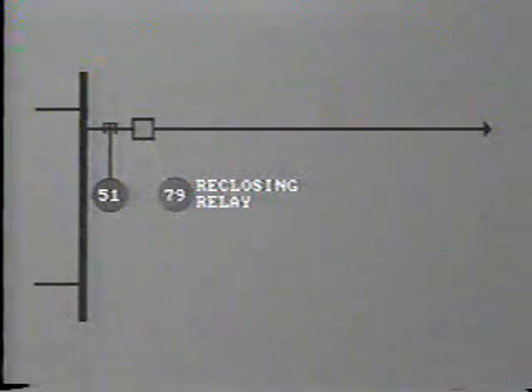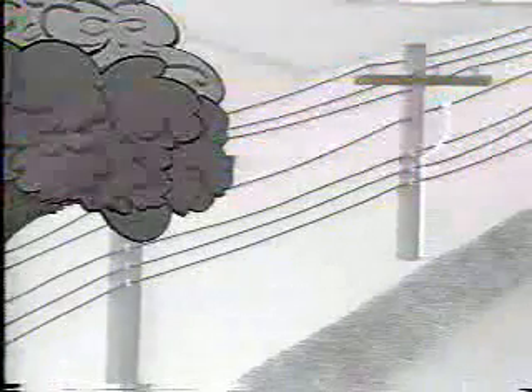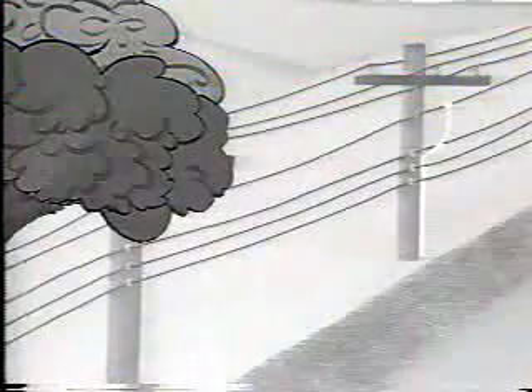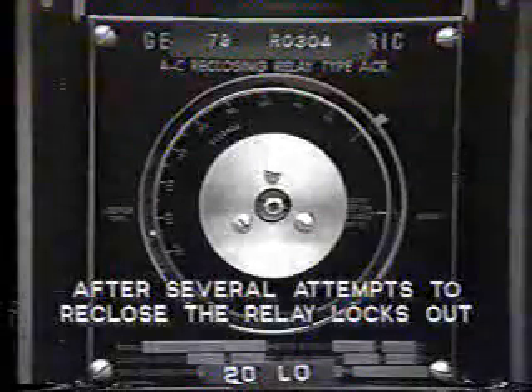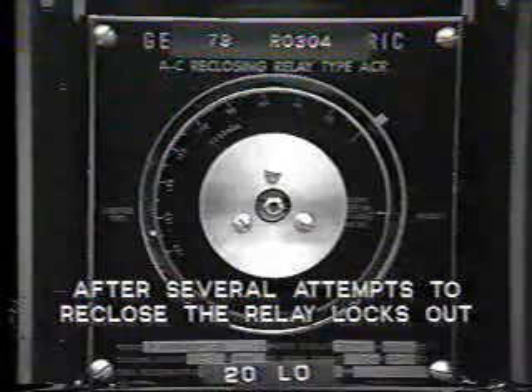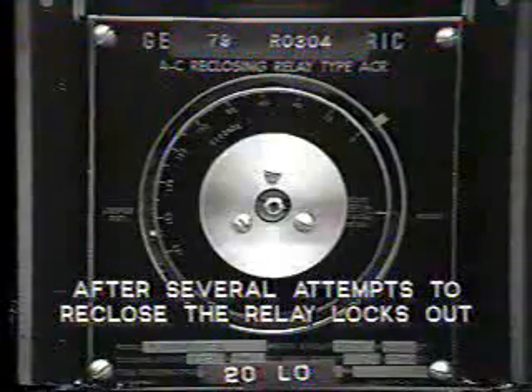Therefore, when the breaker is reclosed by the reclosing relay, the fault will have disappeared and the line can continue operation as normal. However, if the fault is permanent, for example, perhaps a tree limb has fallen onto the line, then the protection will sense that the fault condition persists and will trip the breaker again. The reclosing relay may be set to lock out at this point, or it may be set to permit one or more attempts at reclosing. Now, don't worry too much about memorizing all of the details. We'll be looking at all of this material in far greater depth in future tapes.